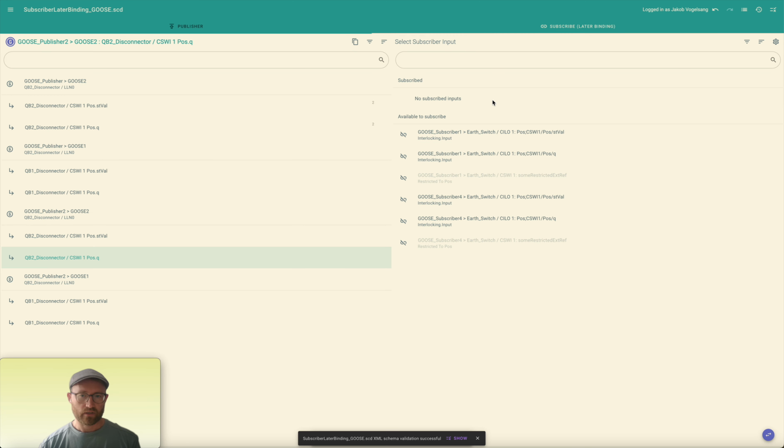When you do unsubscribe, and there is a subscription supervision behind that, we do automatically remove that subscription supervision by either removing the logical node instance LGOS or LSVS if it has been created by this plugin, or adding back the logical node LGOS or LSVS when it already existed in the SCL file and we just edited it.